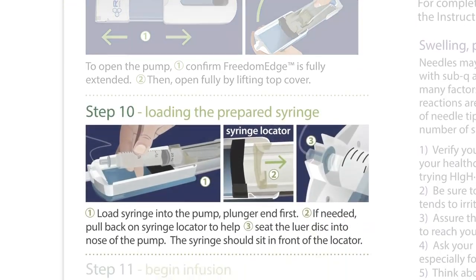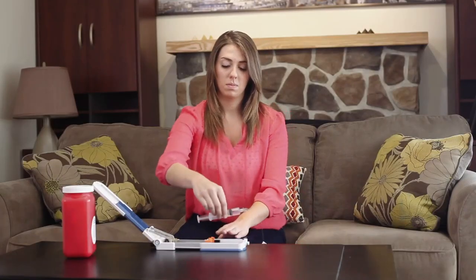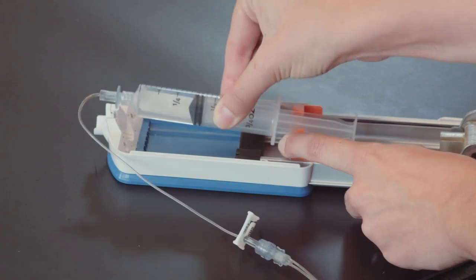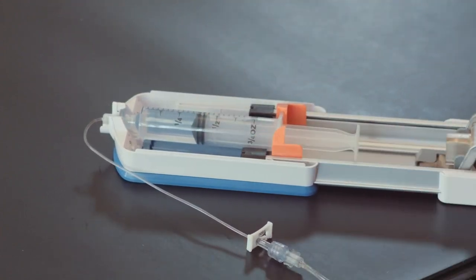Step 10: Loading the Prepared Syringe. Load the syringe into the pump, plunger end first. If needed, pull back on the syringe locator to help seat the luer disc into the nose of the pump. The syringe should sit in front of the locator.